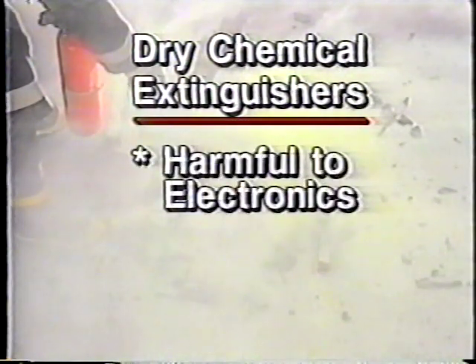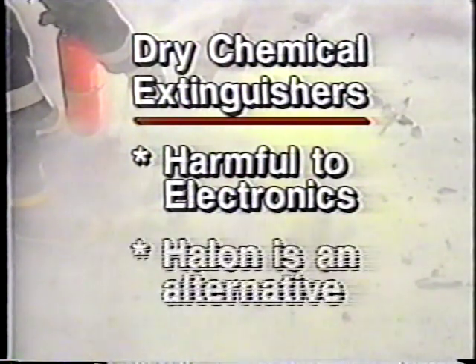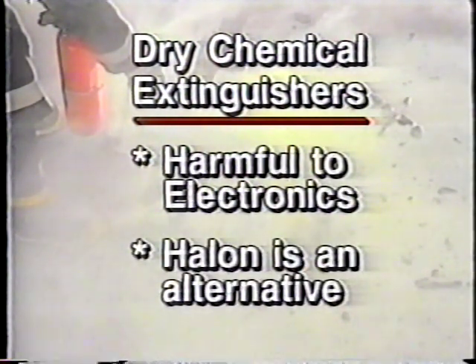When using a dry chemical extinguisher on a Class A fire, you'll need to break up the fire after you've controlled it and coat the hot spots. Dry chemical doesn't cool. It coats and forms a residue which excludes oxygen. If used indoors, a dry chemical extinguisher will create quite a mess and is harmful to electronic equipment. It is not recommended for use on computers. Halon is an alternative agent.